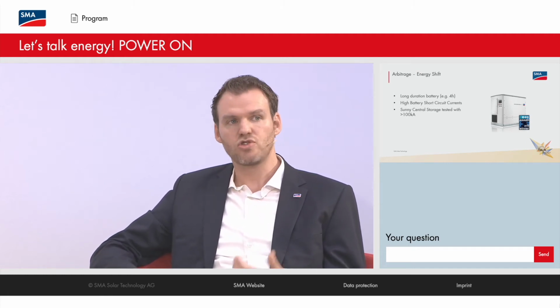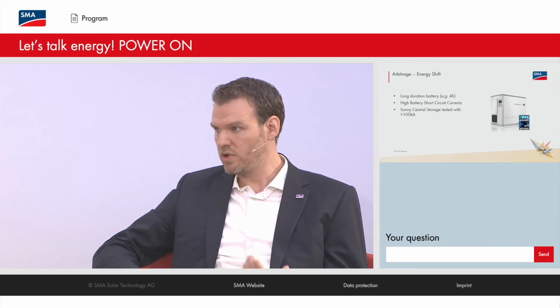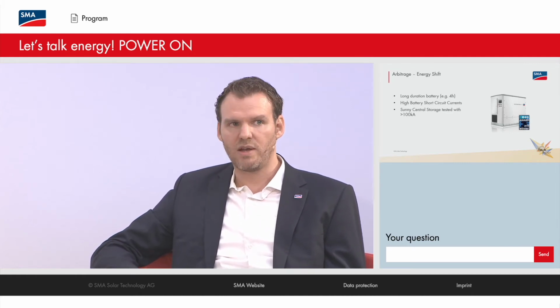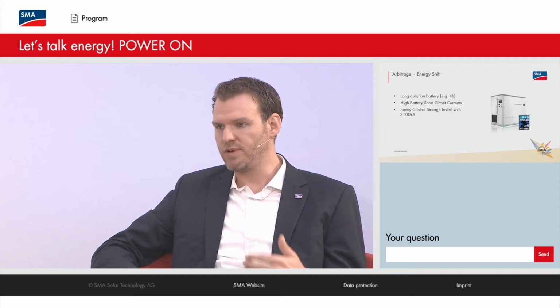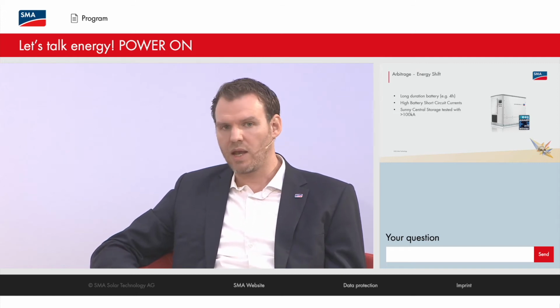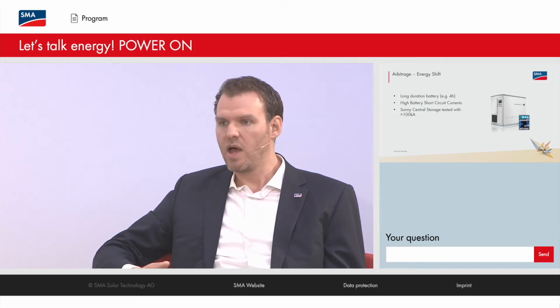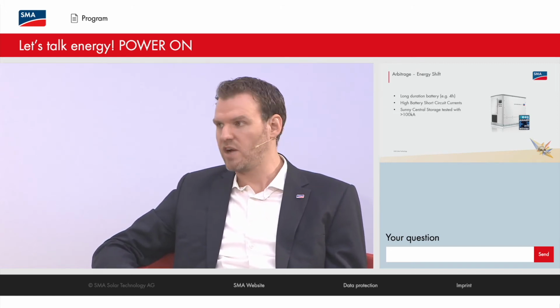We do additional testing for the machine at an institute here in Berlin with more than 100 kiloamps for the inverter to safely trip such a fault. We're also developing a new solution which allows even more than 100 kiloamps, so that for these new applications you can have even larger batteries.